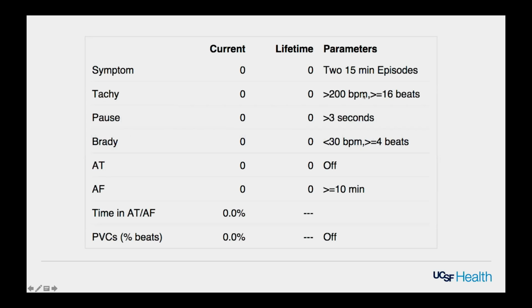Now, the loop recorder is called a loop recorder because it's not recording every heartbeat the patient has. What it's doing is recording a moving window of data. So as it's acquiring new data, it's throwing out old data from maybe 5 or 10 minutes before, such that if the patient either triggers the monitor by placing a device over it or if there is an event that meets certain parameters, the device timestamps that and holds on to that window, maybe 5 or 10 minutes worth of data, depending on the manufacturer, and stores that in memory.